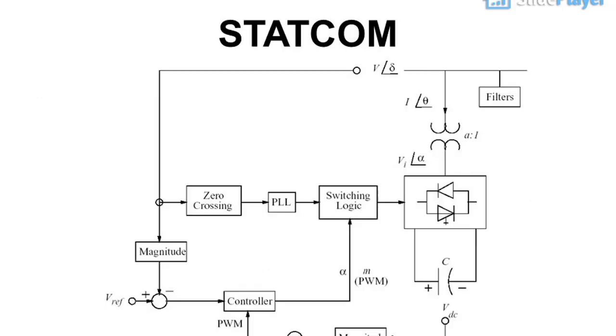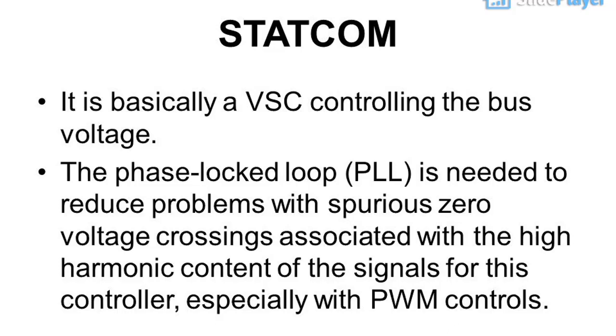STATCOM: it is basically a VSC controlling the bus voltage. The phase locked loop (PLL) is needed to reduce problems with spurious zero voltage crossings associated with the high harmonic content of the signals for this controller, especially with PWM controls.